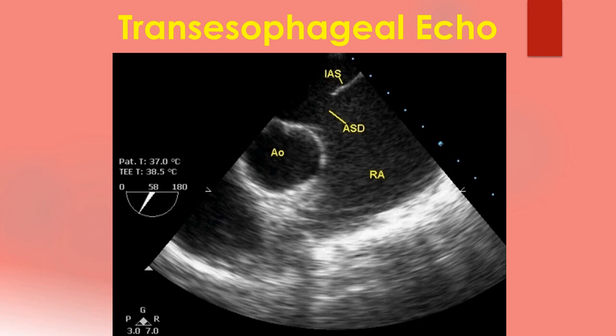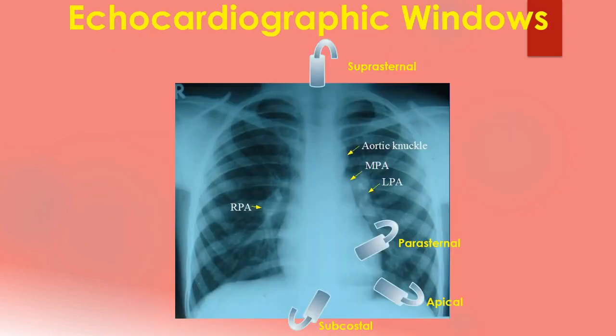Shorter distance permits the use of higher frequency transducers which give better image resolution. Higher frequency transducers have only low depth penetration and are not suitable for transthoracic echocardiography. The four common locations at which the echocardiographic transducer is placed for imaging are the parasternal, apical, subcostal and suprasternal. Parasternal views are often obtained first followed by apical, subcostal and suprasternal. A good knowledge of the anatomy of the heart is needed for interpretation of images from each view, and this becomes more difficult in complex congenital heart diseases where cardiac chamber positions and size may vary.